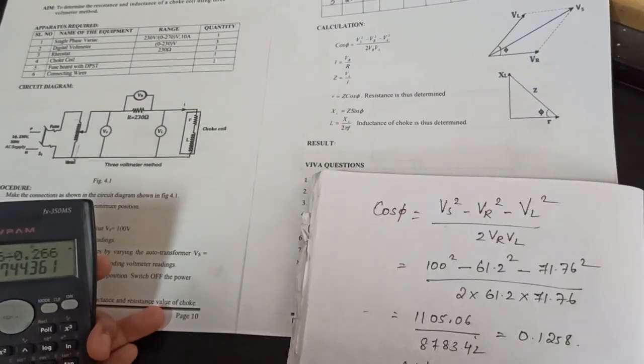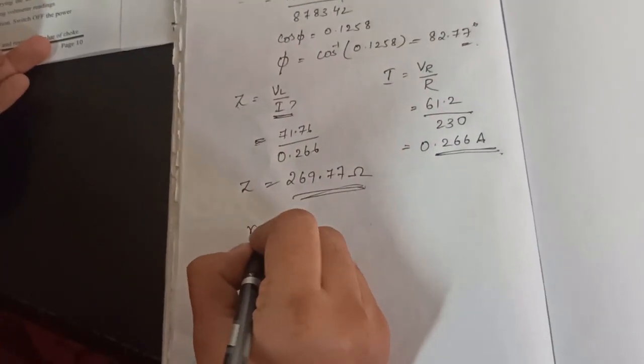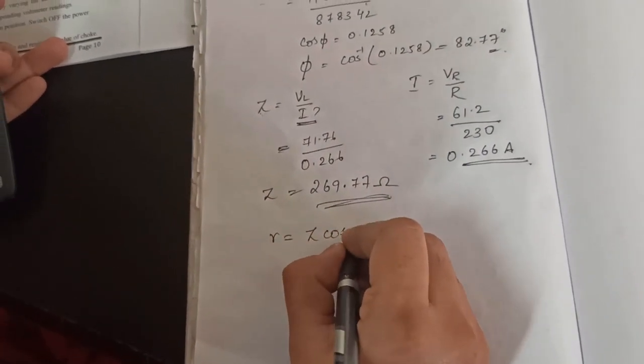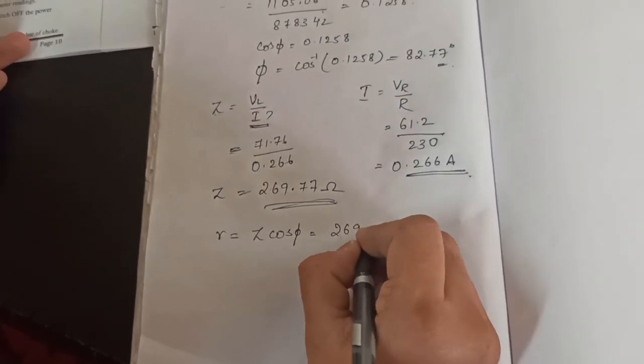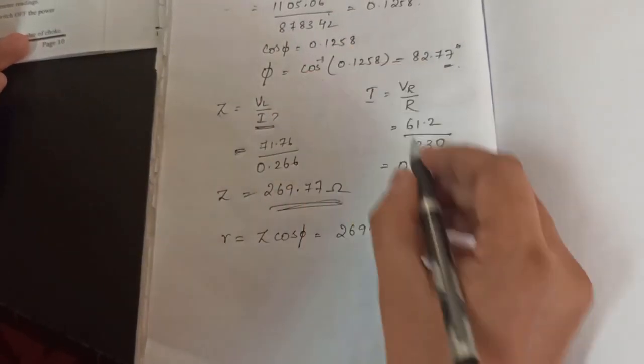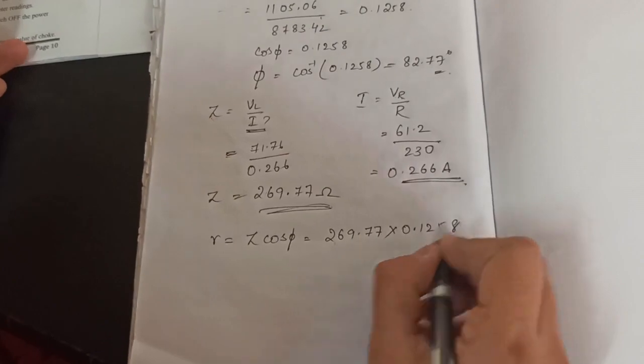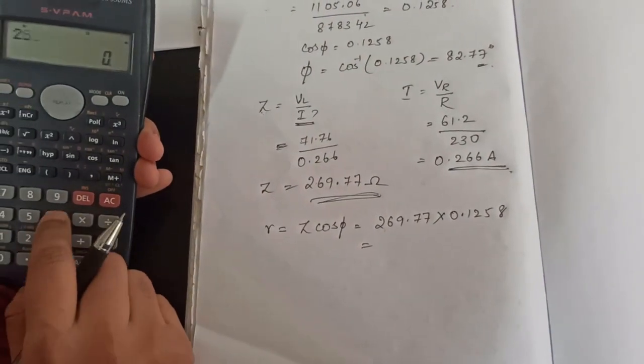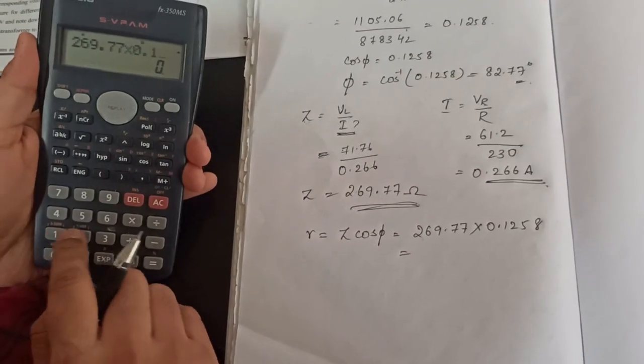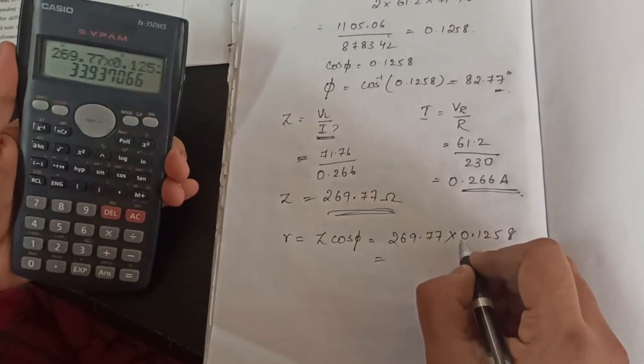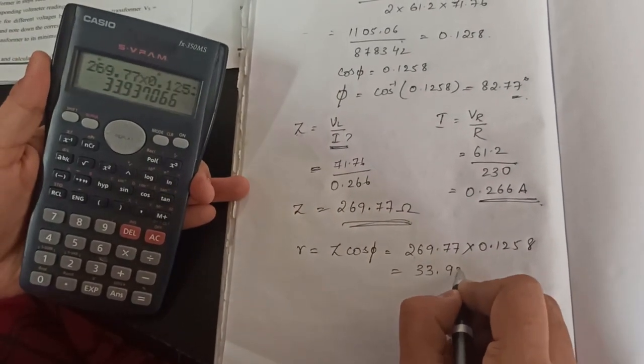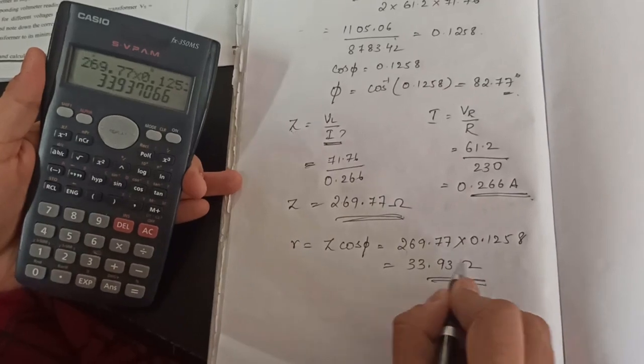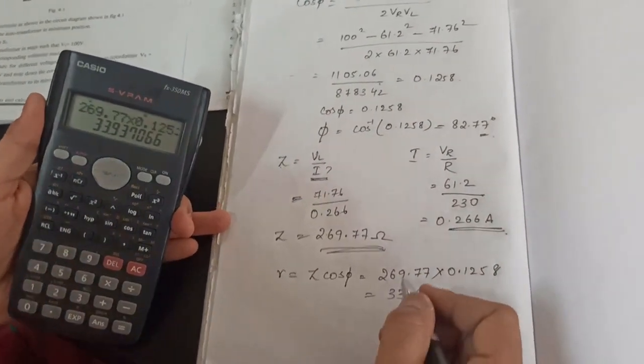The formula is R equals Z cos phi. So resistance of the choke coil R equals Z cos phi. What is Z? 269.77 into cos phi, which we got as 0.1258. So 269.77 into 0.1258 equals 33.93 ohms. That is the internal resistance of your choke coil.